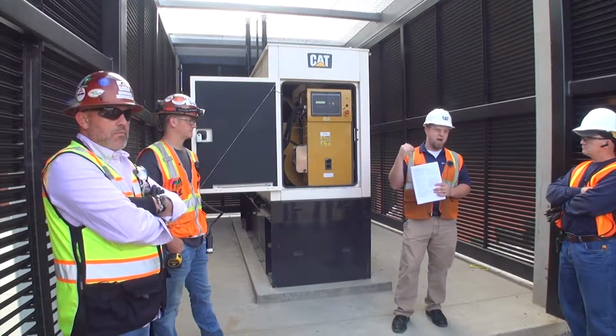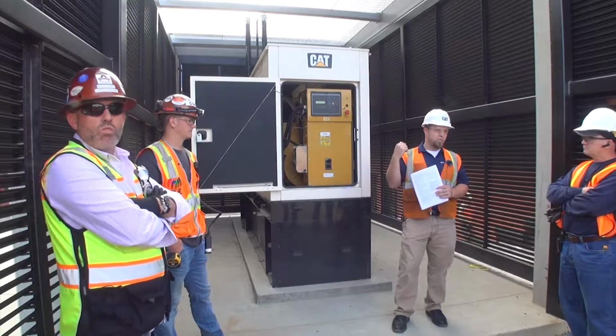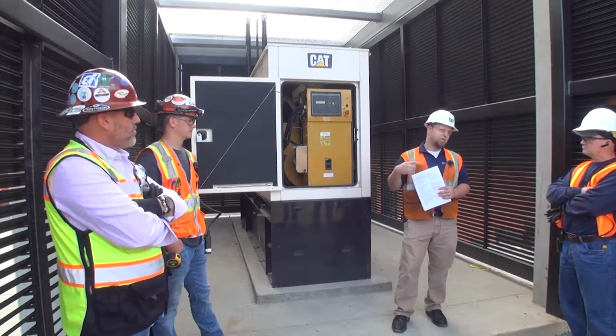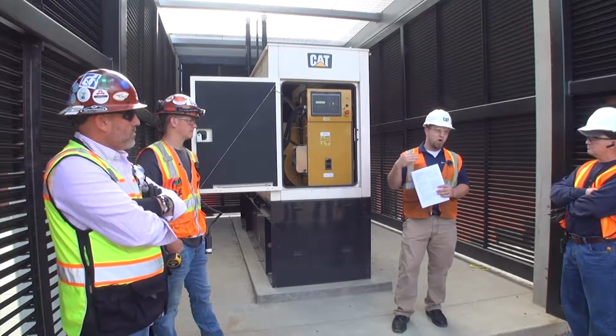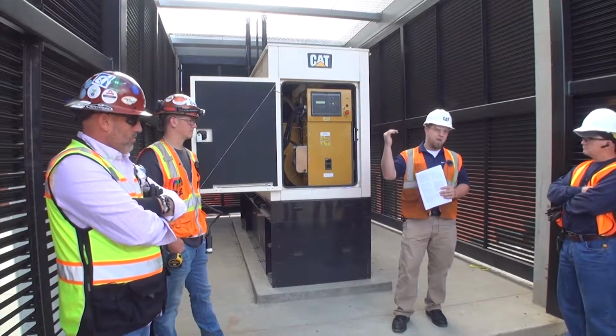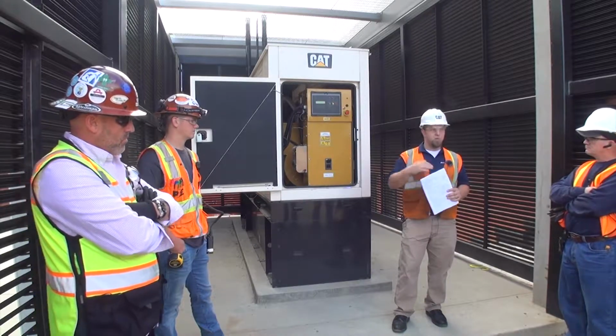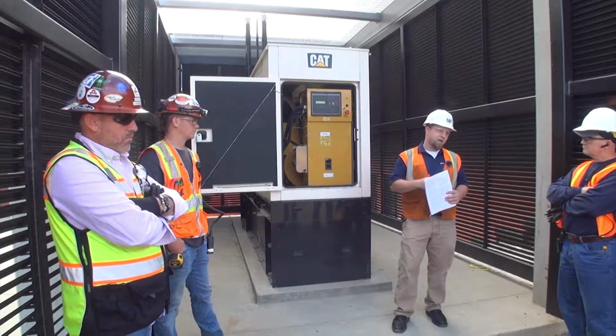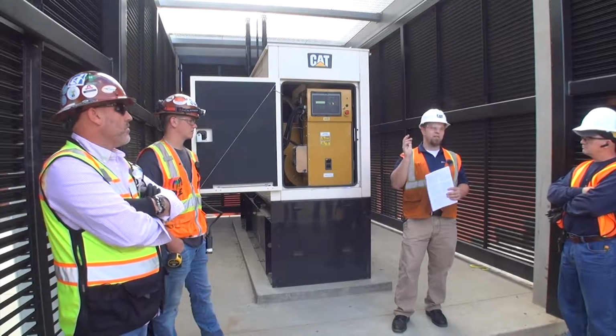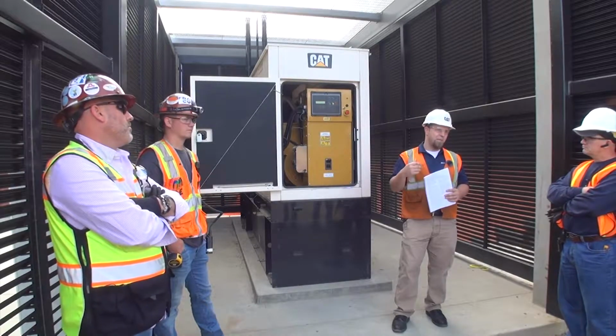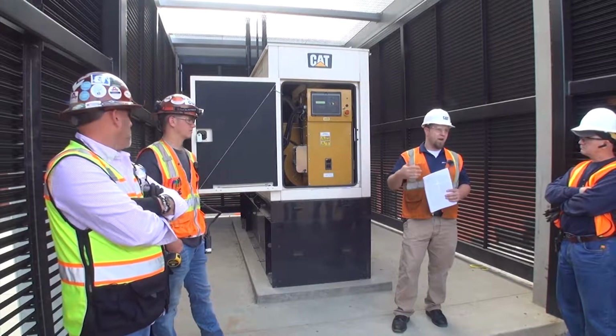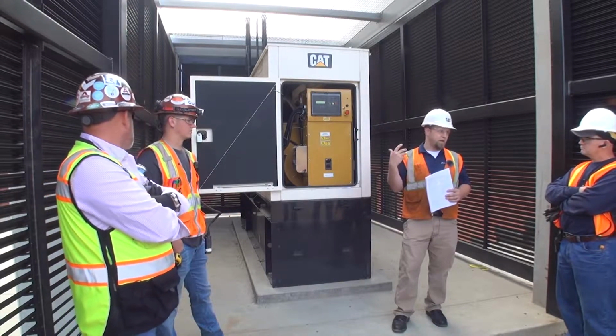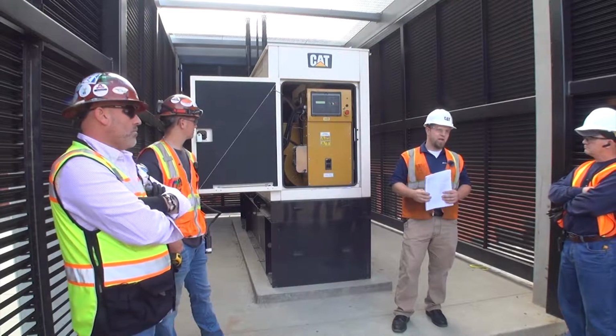These diesels don't have glow plugs, so they're sitting with a block heater running 24 hours a day, and it's just really hard on them—weekly start up, get hot, get cold, then once a month run for 30 minutes under load and come back down. It's not like getting on the freeway and running everything out like a car. That's why you get more life out of belts and hoses on a car compared to these—they're going to get cracked and brittle.